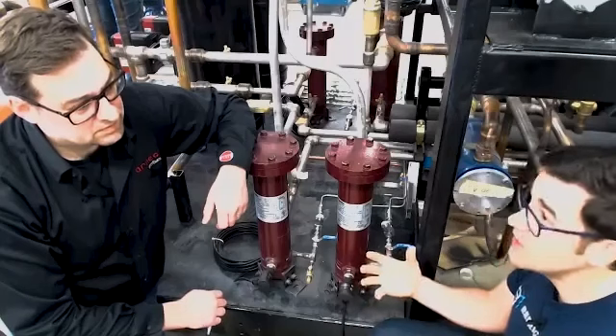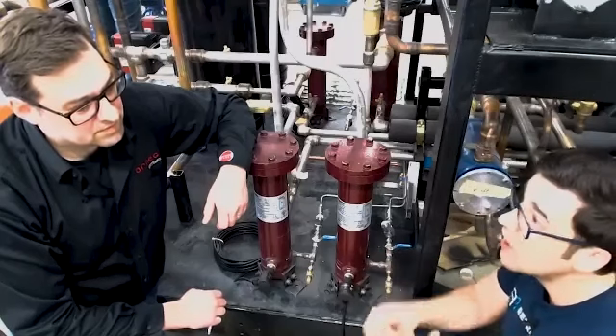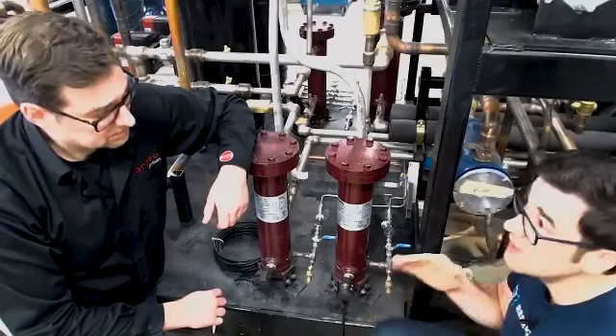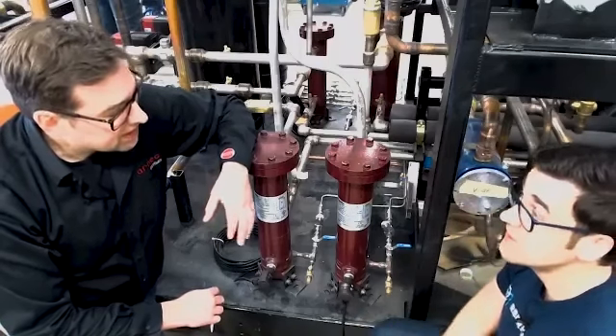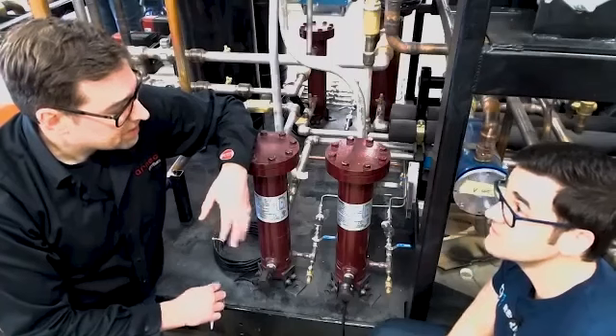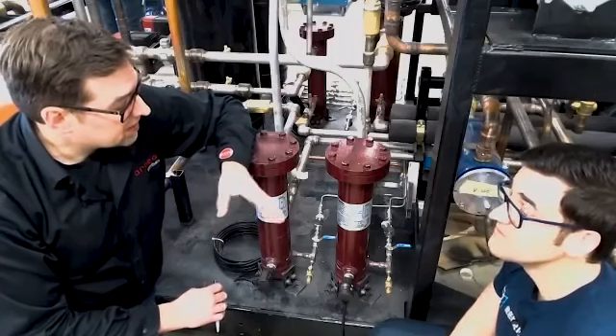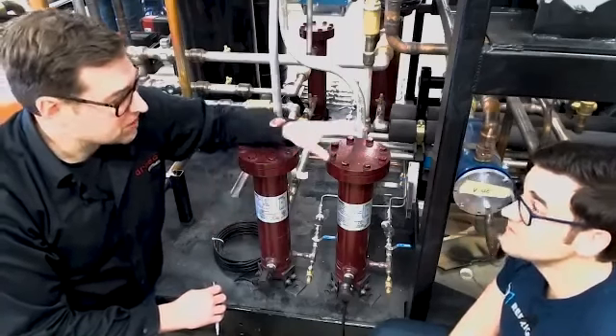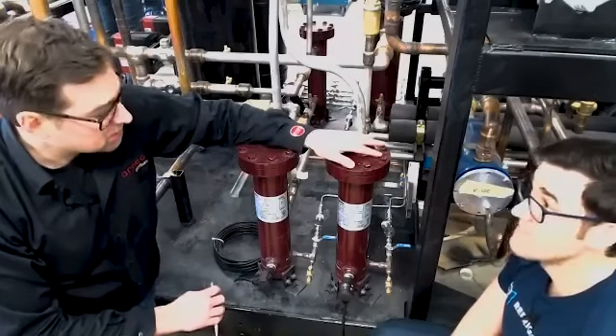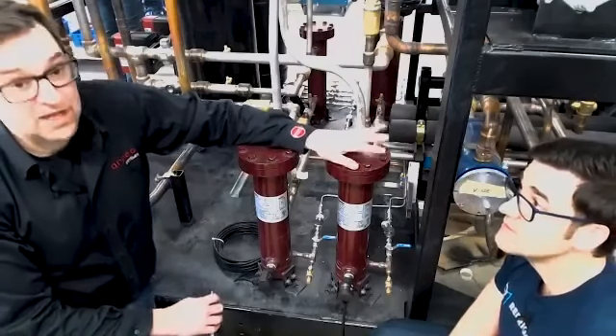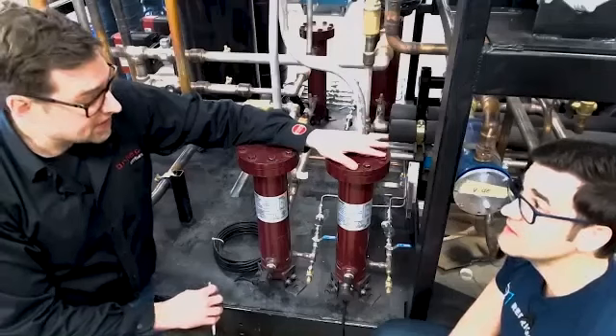These are big applications and a lot of different people work on them. You could get copper filings, moisture, so it's really important to take oil samples. A good rule of thumb is after startup, you give it a good 72 hours, or one week at the most, before changing the oil. Most manufacturers are going to cover that first oil change, so it's essential that it's done.